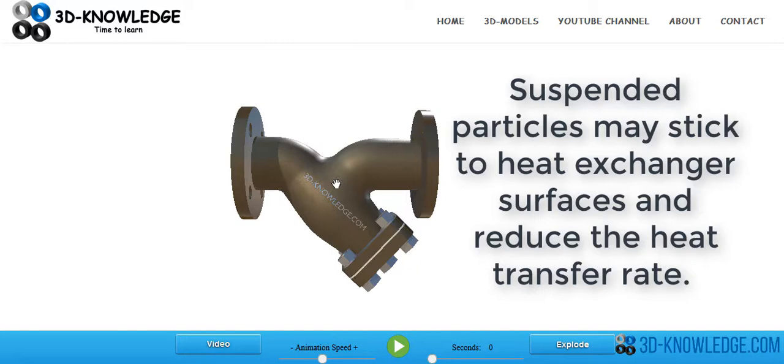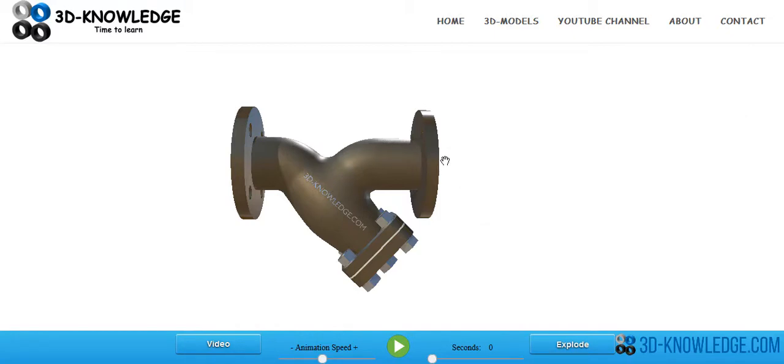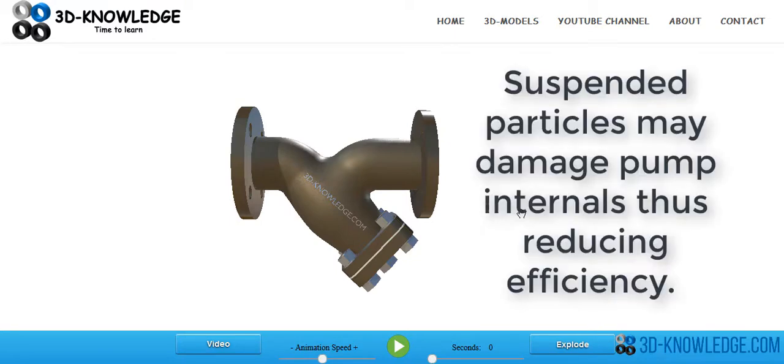If we have fluid flowing in here and then going out the discharge port to a pump, which you can often see, especially in freshwater systems, which this looks very much like a freshwater system filter or a sweet water system filter, what will happen is it will flow to the pump, and any suspended particles, bits of rust, etc., they will foul the pump. The pump internals will no longer work as well as they should.